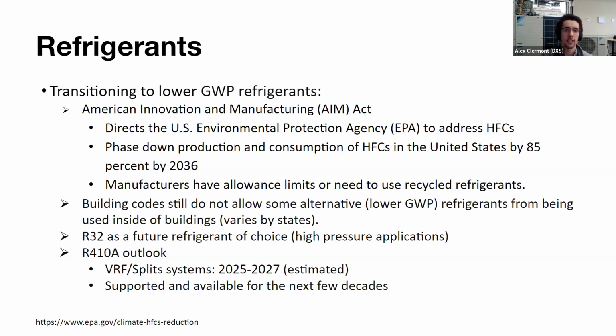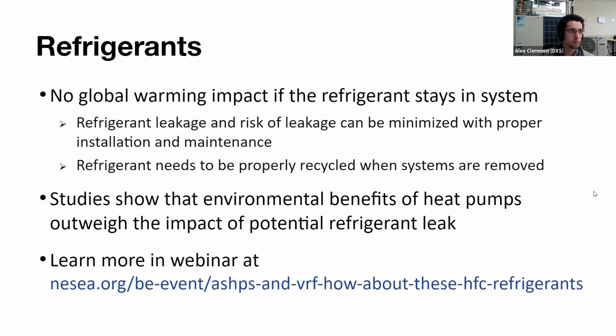With R410A, or with any refrigerant for that matter, there's no global warming if it stays inside the machine it's serving. There's no environmental risk with refrigerants as long as everything's contained in that system. So how do you minimize the impact of refrigerants on the environment? Proper install procedures play a large part in this, and an afterlife program for refrigerants will help as well, allowing recovery of refrigerants into the economy of refrigerants, to be reused on another heat pump technology, which will help reduce environmental impact.